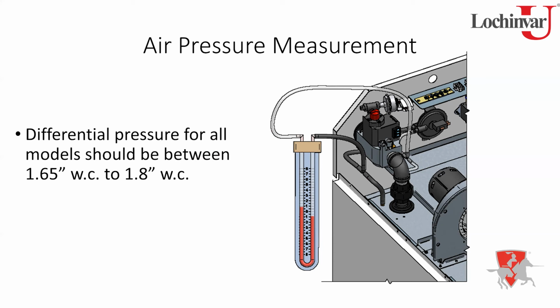Now, the problem is when people come in, they get hung up on that differential pressure. They say, oh, the low air pressure switch isn't making. So they measure the differential pressure, and they see it isn't where it's supposed to be. The first thing they want to do is grab the air shutter, which is right over here on this fan. They loosen the 2 screws and pull that air shutter wide open, so you put more air down into that front cabinet. Now your differential gets closer.